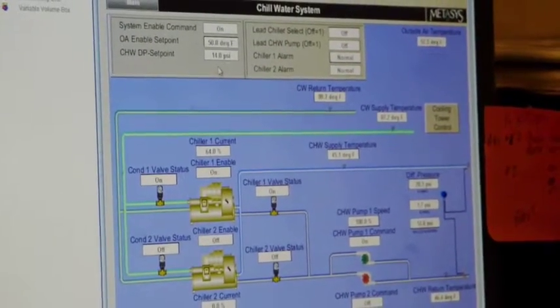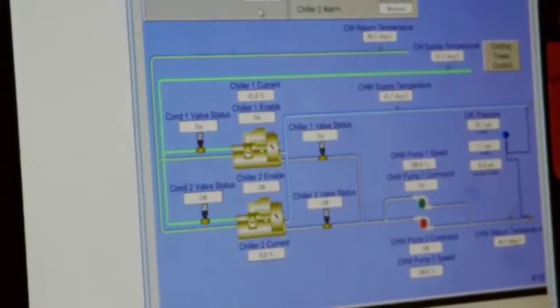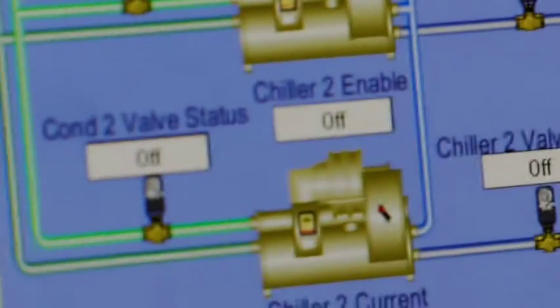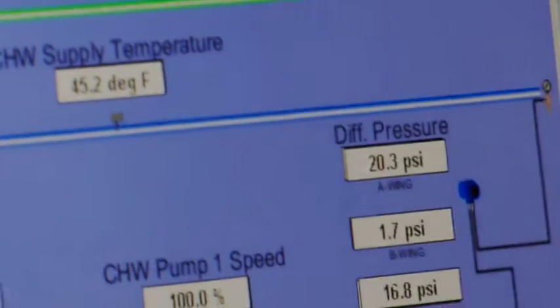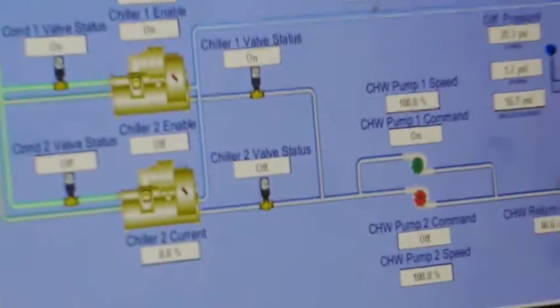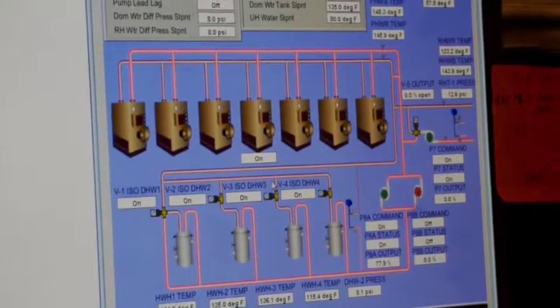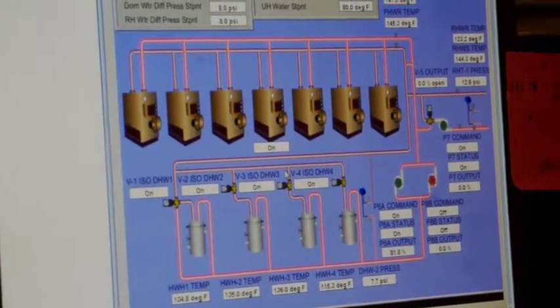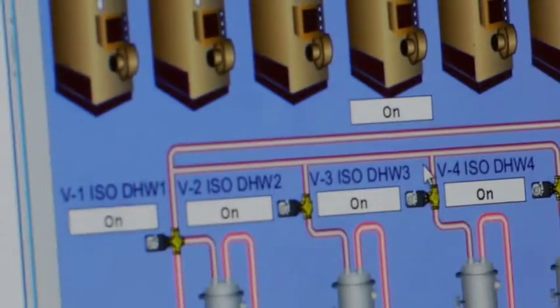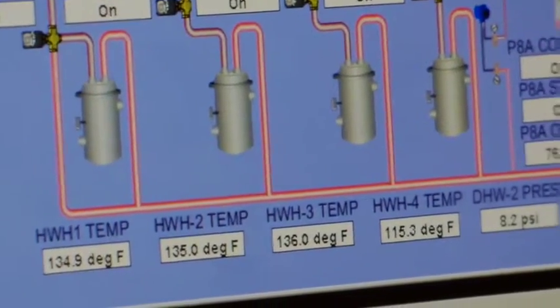So this is downstairs. We have 2 chillers, and so this tells us our supply of chilled water coming in. This tells us the temperature of water going in, the temperature of water going out. It tells us what pumps are on, what percentage of the pump speed is actually on. When you have a mild day, say 50 degrees outside, you may use a little of the outside air versus what's inside, so you won't use a lot. And so this kind of tells us what we're using, and it gives us a system. So we supply hot water to both A, B building and the clubhouse area. That does the laundry, that does the dishes in the kitchen, and then all the residence places as well. I need hot water, so we have 5 holding tanks downstairs, and those holding tanks hold that water and maintain it at 148 or 150 degrees.